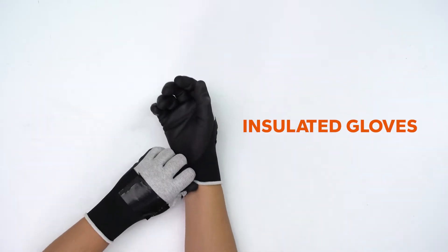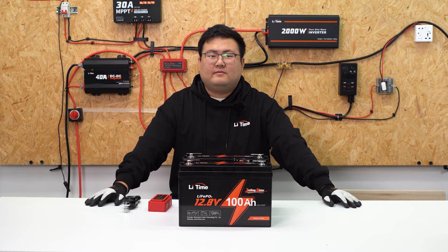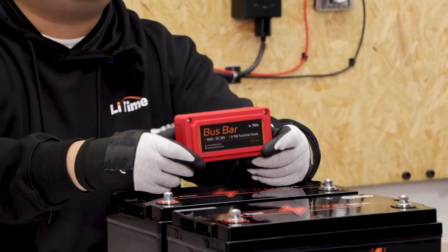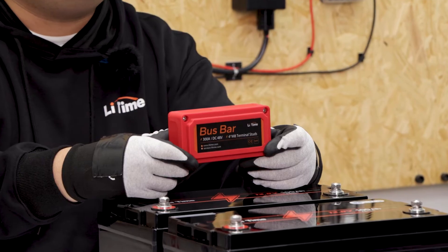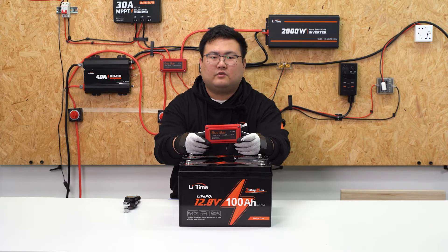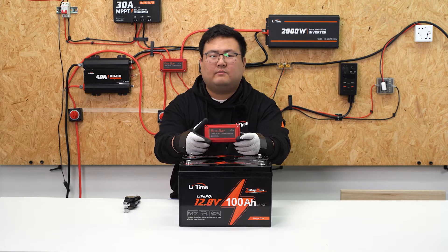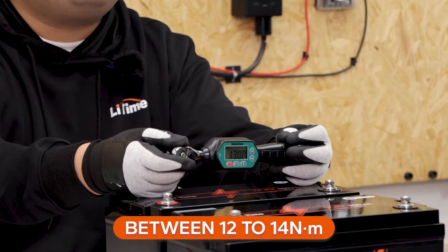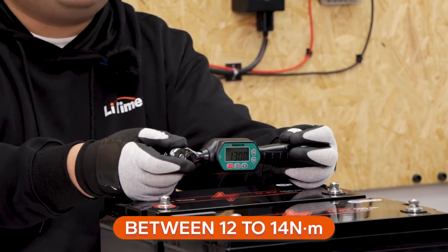Please wear your insulated gloves throughout. Now let's get started with parallel connections. We suggest using the copper bus bar, as it balances the input and output currents of each battery to protect connected terminals from heating up or even melting. During the connections, use a torque range of 12 to 14 Nm to tighten all the bolts securely.